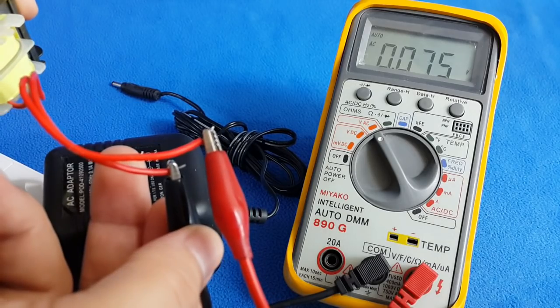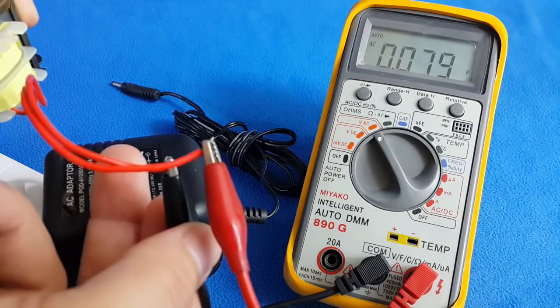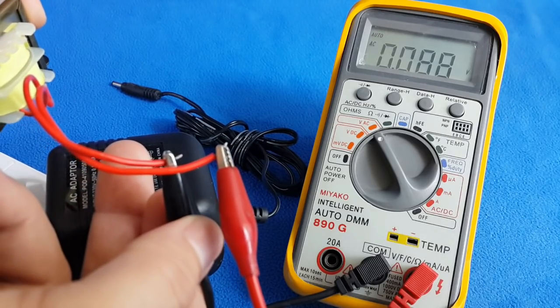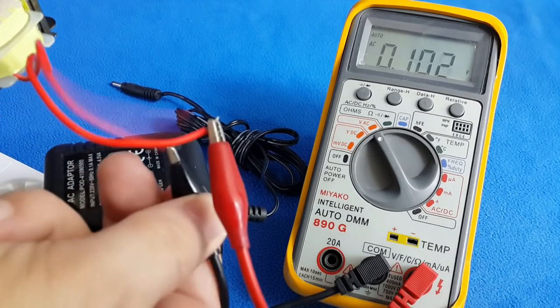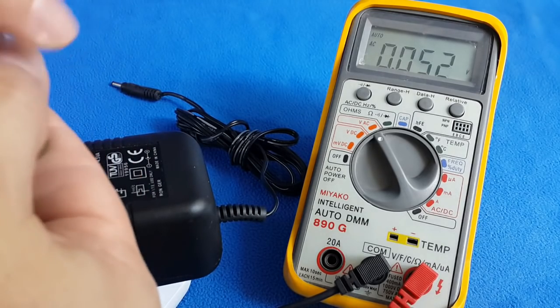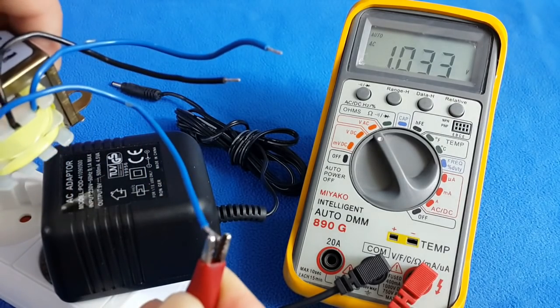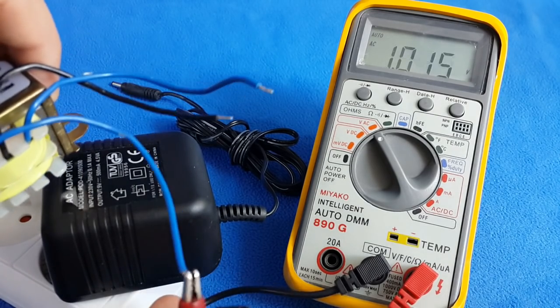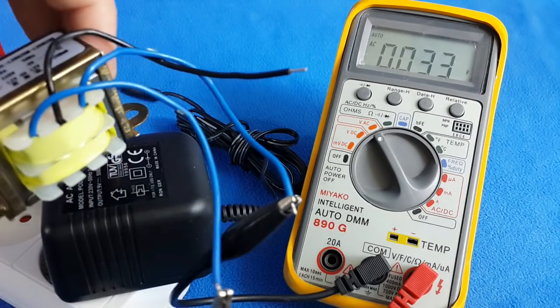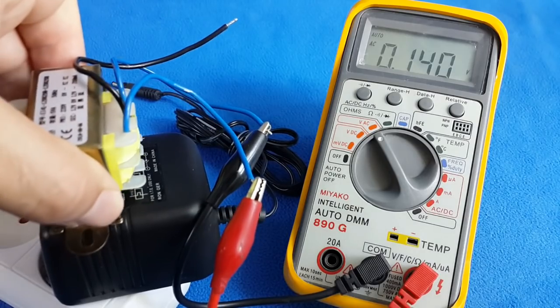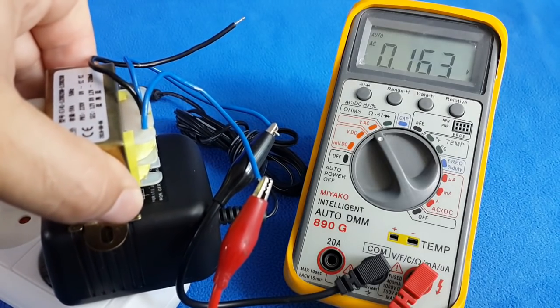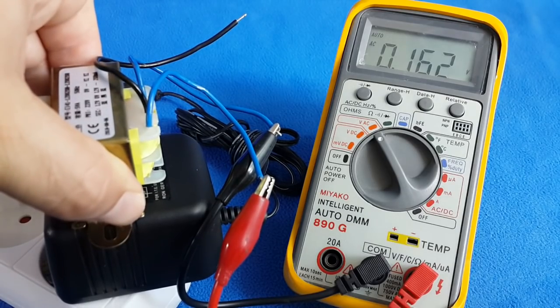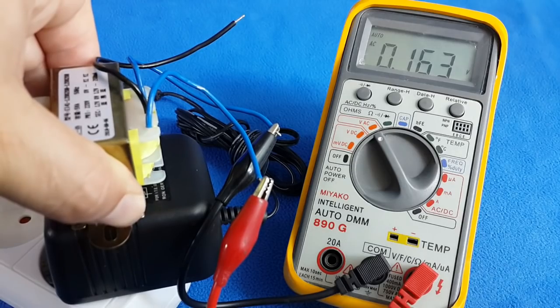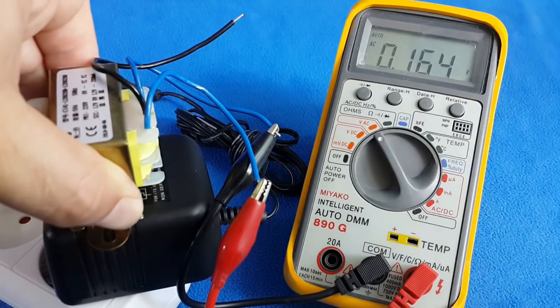My transformer is 240 to 24 volts, so I could expect a voltage reduction on a ratio of 10 to 1. It will always be a little bit more because transformers have very low efficiency. They will lose 15 to 20% in heat, vibration, and the field. So in this case, that's the little difference I see here without any load. But the ratio is okay.